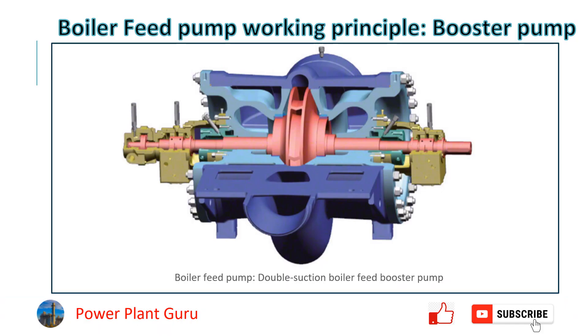If you are generating steam at 105 to 106 bar, then there has to be a little higher pressure at the discharge of the BFP so that water can travel from the BFP to the boiler economizer or the steam drum. At the boiler feed pump you will have around 10 to 15 kg extra pressure so that, accounting for all losses, water from the BFP can reach the economizer and steam drum.